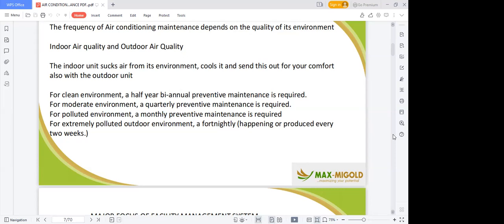So the indoor unit sucks air from its environment, cools it, and sends this out for your comfort. Also with the outdoor unit. So the indoor unit actually cools the air within the space. It does not bring air from outside. It is what you give it that it cools. If the air is of poor quality, it takes the poor quality air in and brings the poor quality air out. So in order to purify the air, you need what they call a ventilator, or you find air units that you have to install to purify and remove the dirt within the environment.